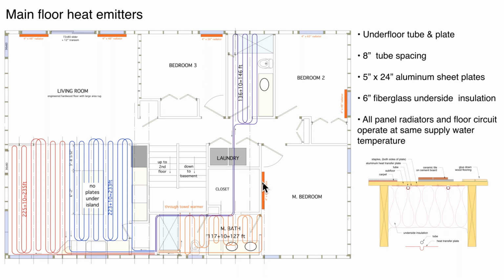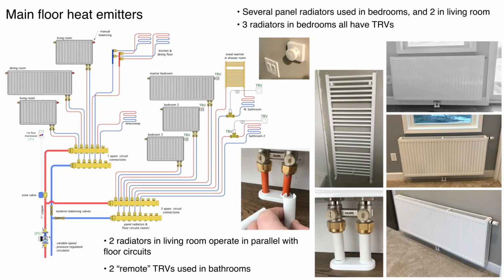So far, we've looked at 3 different heat emitters, slab on grade radiant, below floor tube and plate, and then these heat emitters, okay? Radiators. Here's the layout. You'll see some of the panel rads here have the thermostatic valves on them. There's a towel warmer in the master bathroom that has a thermostatic valve, but it's not on the towel warmer. It's actually under the floor with a capillary tube up to that device right there. So it does the same function, but it just isn't mounted directly on the towel warmer.